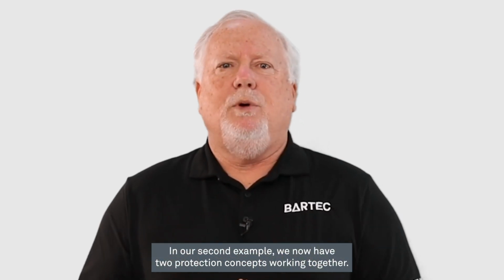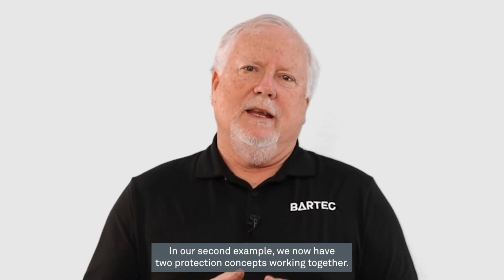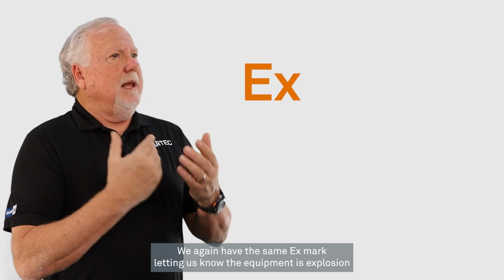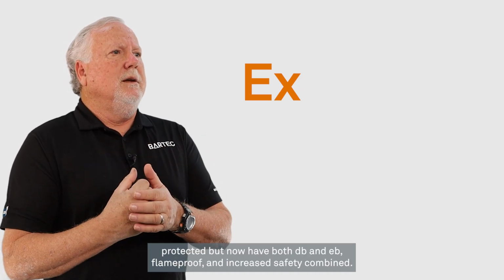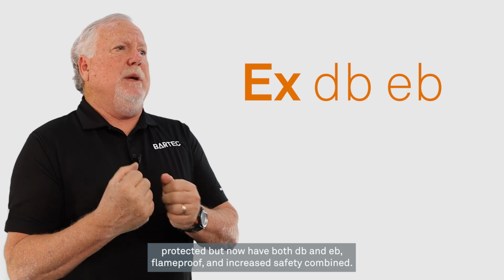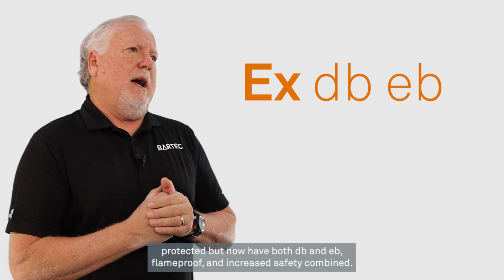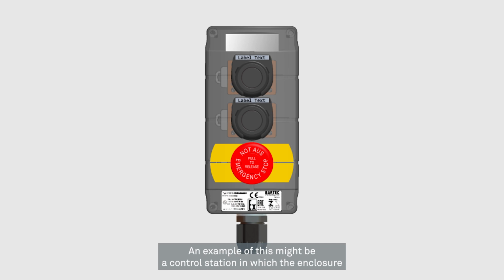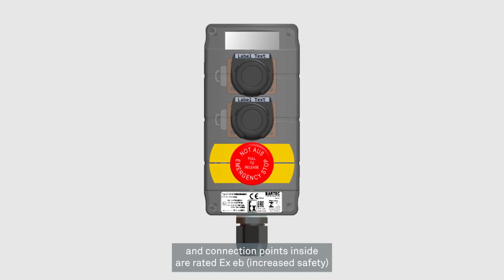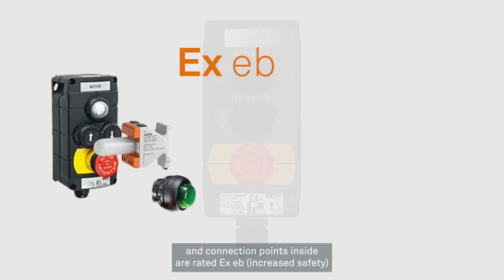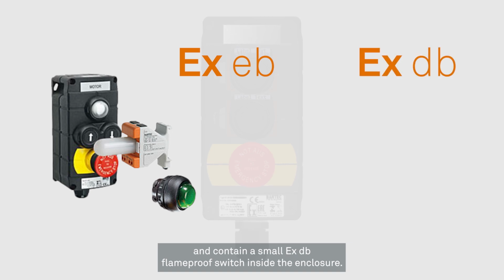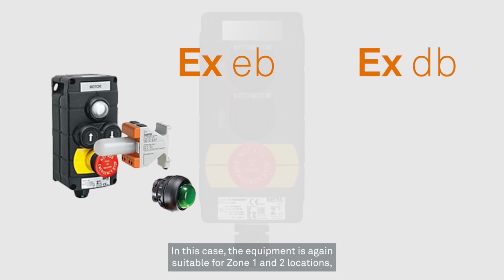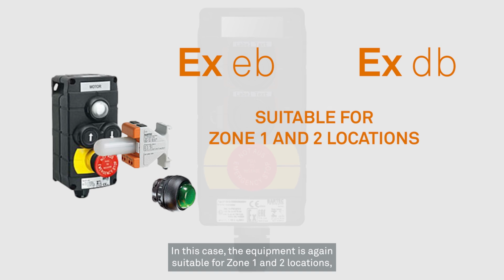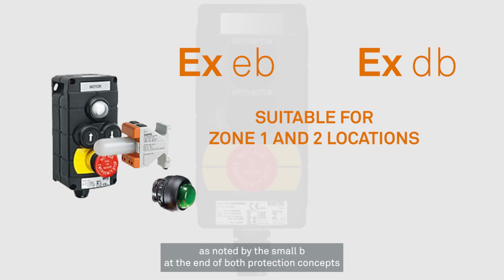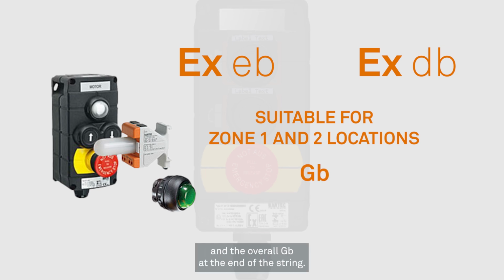In our second example, we now have two protection concepts working together. We again have the same EX mark, letting us know the equipment is explosion protected, but now we have both db and eb, flame-proof and increased safety combined. An example of this might be a control station in which the enclosure and connection points inside are rated eb, increased safety, and contain a small Ex db flame-proof switch inside the enclosure. In this case, the equipment is again suitable for Zone 1 and Zone 2 locations, as noted by the small b at the end of both protection concepts and the overall Gb at the end of the string.